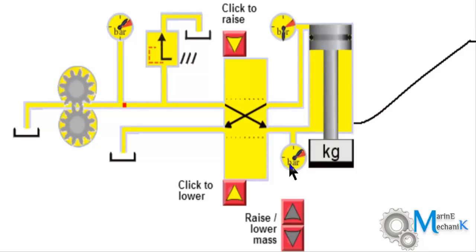You can see the pressure here. Pressure here reaches maximum pressure after which no more oil will flow where the safety pressure relief valve safeguards the system and thus avoids any rupture of the pipelines.